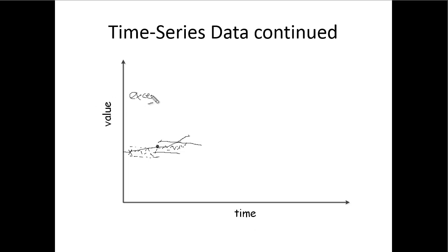Okay, and one of the nice things about that is that I can specify this deadband. And so this allows me to filter out noise. Maybe I have a signal and I'm getting noise in the signal, right? It's a bunch of little stuff like this. And then something happens, and then there's a bunch of noise in here. Okay, well maybe this little deviation in here just isn't important to me. I know it's noise, it's not important. And so what I really want to store in my historian is a cleaned up signal that looks like that. Okay, so that's why I would define a deadband.